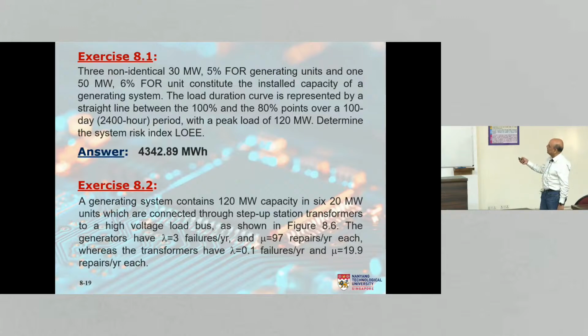So another exercise for you: 3 non-identical 30 megawatt, 5% forced outage rate generating units and a 50 megawatt, 6% forced outage rate unit constitute the installed capacity of a generating system. So it's 3 times 30, 90, plus 50, 140 megawatt. The load duration curve is represented by a straight line between 100 and 80% over the 100-day period with a peak load of 120. Installed capacity is 140, the peak load is 120. Determine the system risk. Okay, similar to the 2 examples that we have seen just now. I'm sure you can do it, so there is an answer as well. Not sure if you can do it this afternoon because you have some demonstration of software, but hopefully you'll make time later on to check it out.